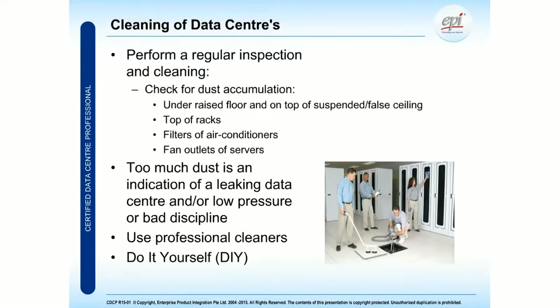With dark colored racks, like black racks, it's quite easy to see dust on top of the racks, but it's very difficult to keep it out of the data center altogether. The filters also need to be cleaned every now and then, and too much dust is an indication of a leaking data center. We also talk a bit about pressure levels inside the data center, since operating at the right pressure will help prevent dust from entering the server room.